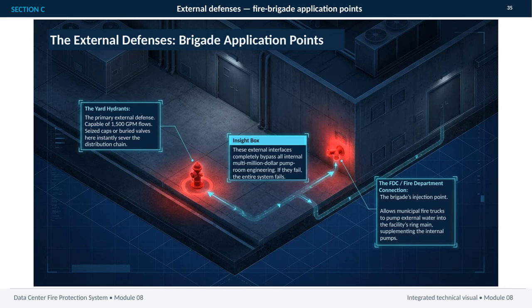The first application point is the yard hydrant. These are the primary external defense, with the capacity to deliver flows of up to 1,500 gallons per minute. That capability is only useful if the hydrants remain accessible and operable. A seized cap or a buried valve can immediately interrupt the distribution chain, preventing water from reaching the intended point of use. The second application point is the fire department connection, or FDC.